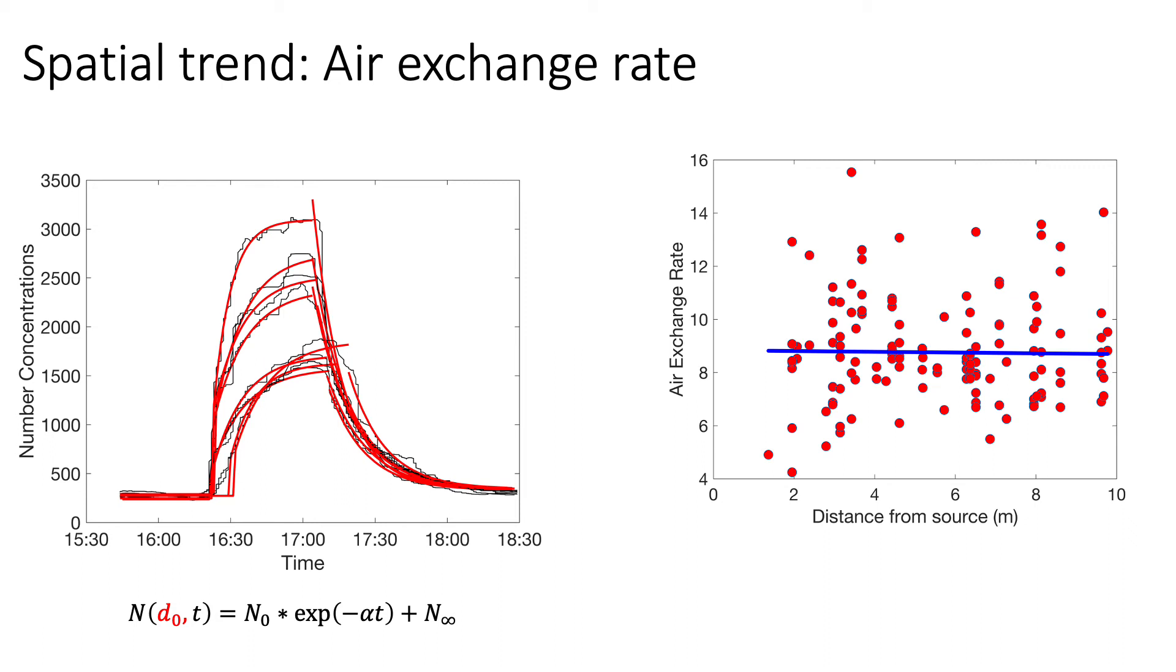What we found was that for sensors as a function of distance from the source, there's a lot of variability in what the air changes would be. But on average, we found that the air exchange rate was largely unchanged from the front of the room to the back of the room, at least for this one classroom. This suggests that the general behavior of a well-mixed room is somewhat applicable. Particles that are climbing up decay at the same rate throughout the room. But it's not entirely well-mixed. We can see very clearly the concentrations in one sensor are very different from one somewhere else.